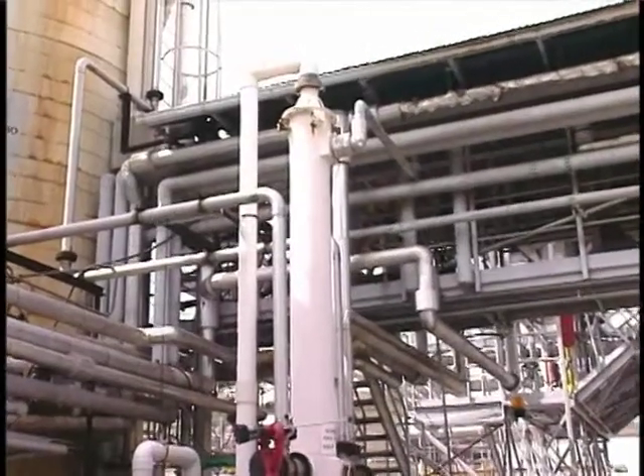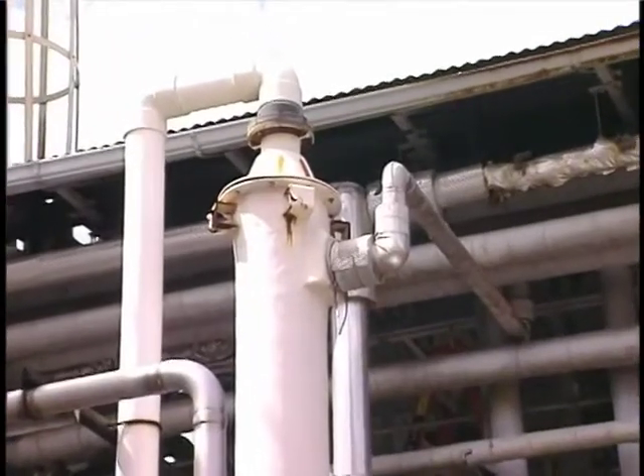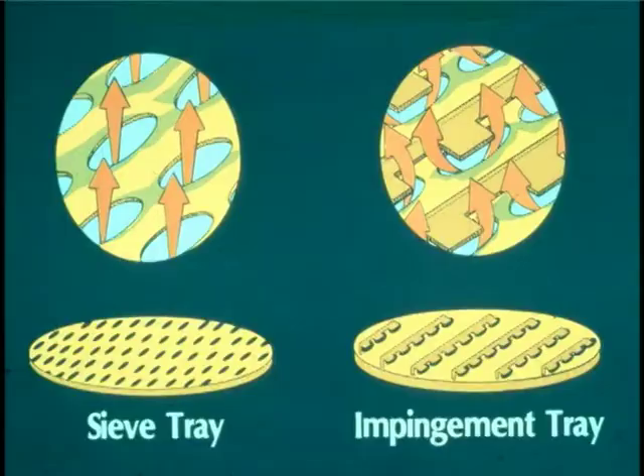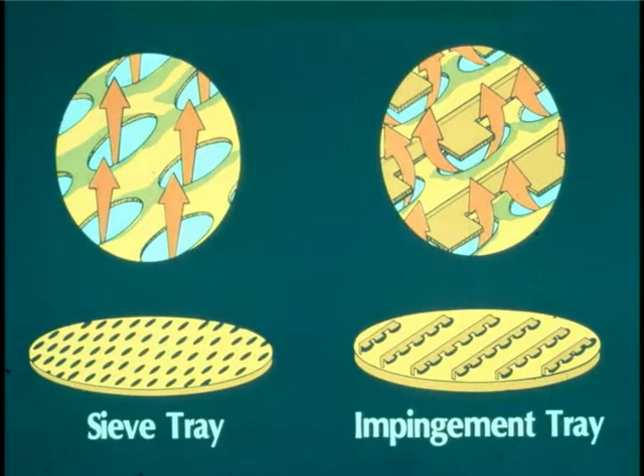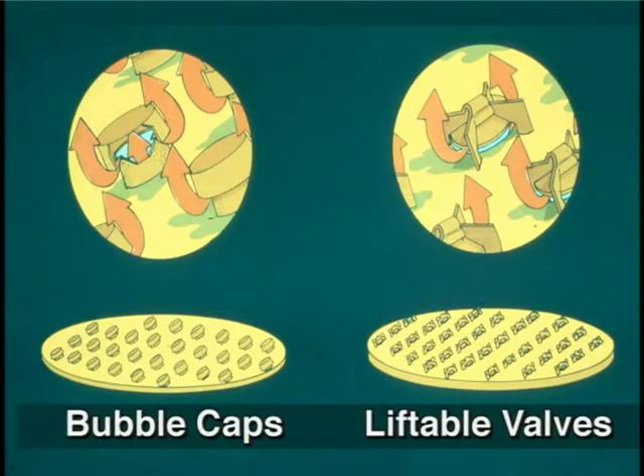The tray tower is a medium energy scrubber and consists of a vertical column with one or more trays mounted horizontally inside. The simplest tray is a perforated plate referred to as a sieve tray. Other tray designs include impingement trays that have small impingement targets above each perforation to enhance gas-liquid contact, bubble cap trays that can operate over a wide range of gas and liquid flow rates without adversely affecting collection efficiency, and valve trays that have liftable valves or caps that improve gas-liquid contact when the gas flow rate varies.